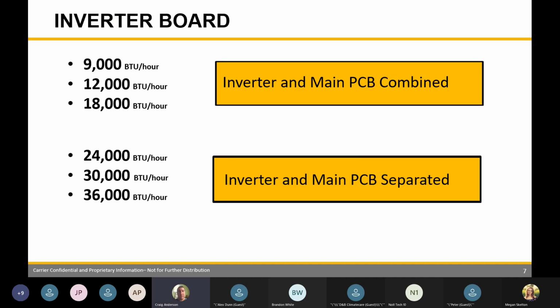So on our inverter boards, our 9, 12s, and 18, the boards are together. Your main board and your power board are all in one board. When you get to the bigger units, the 24s to the 36, the inverter board and the main board are separate. So things to look at, you're going to have 2 boards in the bigger units. The smaller units, you're only going to have 1 board located in it. And yes, some are going to be upside down, some are going to be upside right. And we'll go over that in some of the pictures as well.